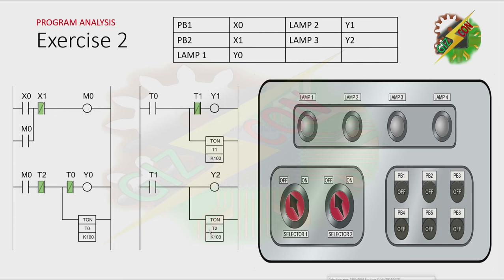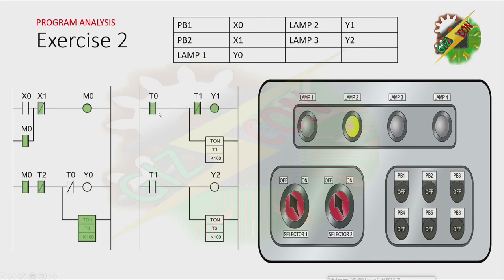This will be my answer to this exercise. Let's have our analysis for this program. By pressing PB1, M0 will turn on, and because M0 is on, it will not turn off unless we press PB2. And because M0 here is on, and T2 here is on, and T0 here is on, that will make Y0 to turn on. And timer 0 will turn on after 1 second. Then because timer 0 is now on and this contact is on here, that will make Y1 to turn on. And timer 1 will turn on after 1 second.